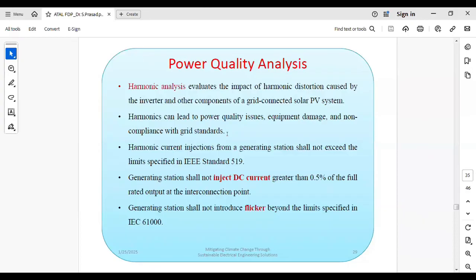How much voltage harmonics, how much current harmonics, how much DC current you are injecting into the grid, and what is the voltage flicker, what is the allowable percentage. Those things, according to CEA, you have to verify, whether you are satisfying all the terms specified in the Indian grid code, so that you have to justify at the point of interconnection.